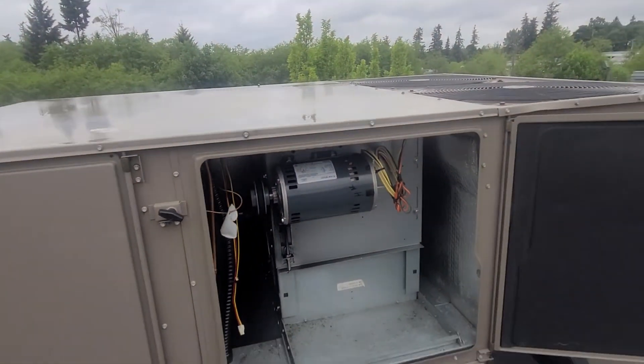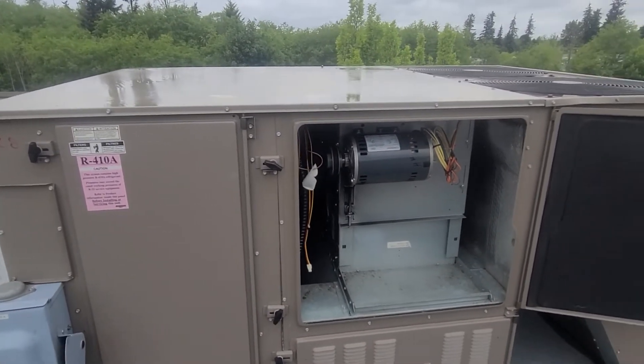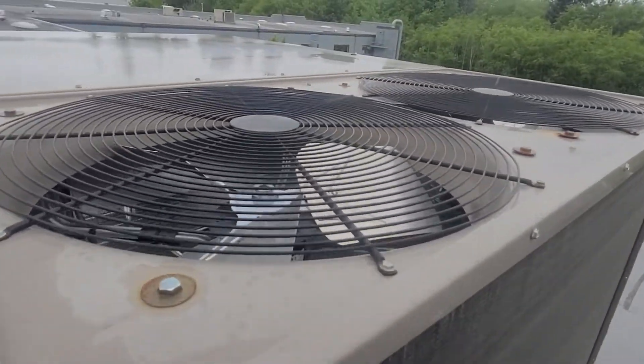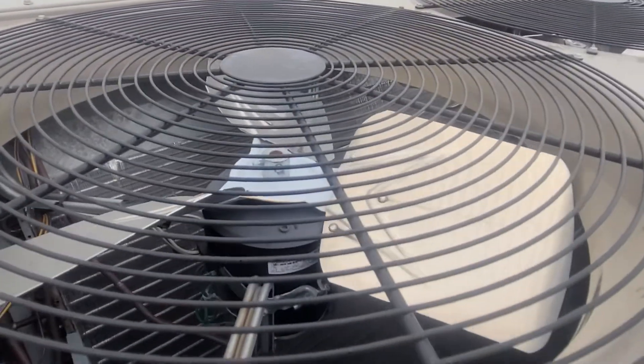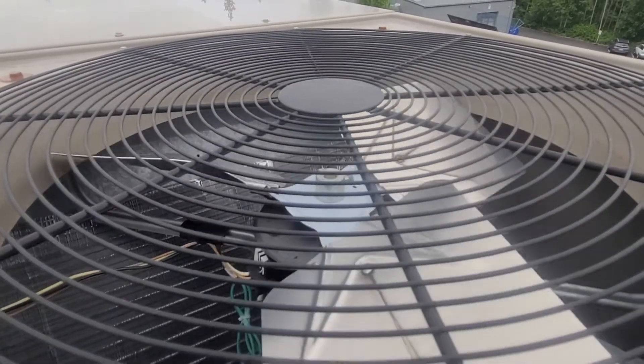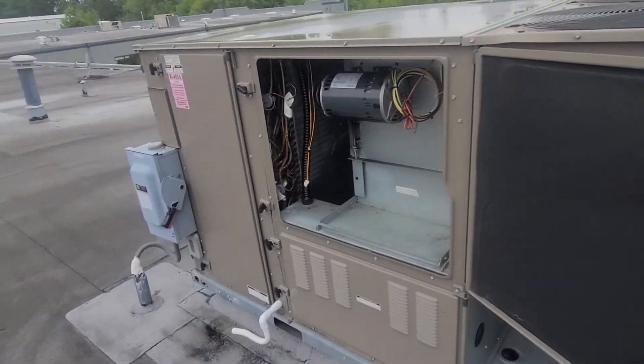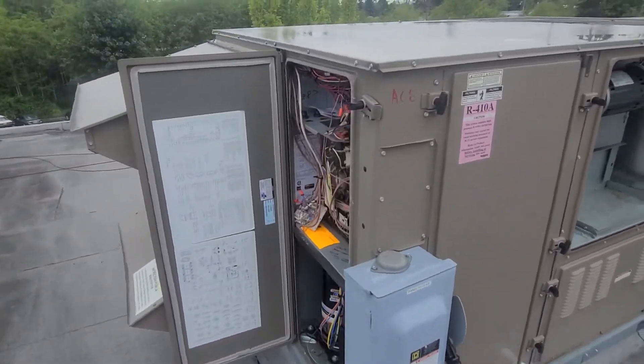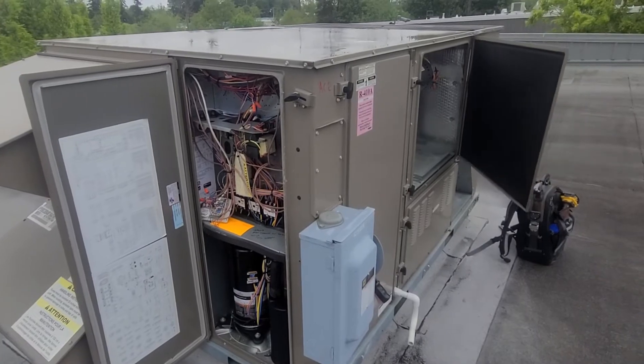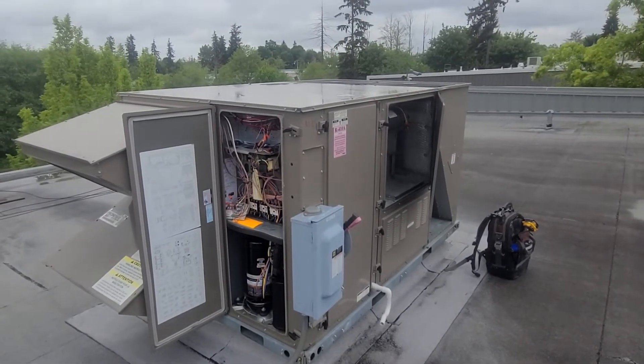I'm definitely writing up a new belt and I'll make some adjustments — it's pretty easy to do by loosening some bolts and adjusting up or down to set the tension. I think it might just be slightly out of alignment, so I'll take a look at that. Now that I've got the panel off, I'll further inspect the blades. I'm also probably going to try to cycle it into a defrost cycle just to make sure everything checks out. That's pretty much where I'm at with this one — if you like the video, give it a thumbs up, please subscribe, and thanks for watching.